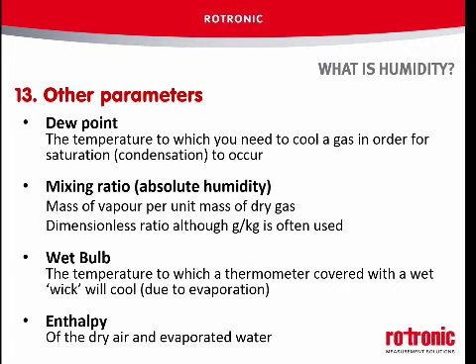Traditionally, for reasons as to how they were measured, or different instruments, or different engineers doing different things, the key point is that most modern instruments can now measure humidity and temperature, and they will give out these outputs if you need them. So if you have a control system that requires an enthalpy input, your instrument supplier will almost certainly be able to supply an instrument that is configured to provide that analog output, or that digital output. So you can hot swap, essentially easily swap in a new instrument without having to rely on some ancient old instrument that is designed to measure wet bulb, perhaps.